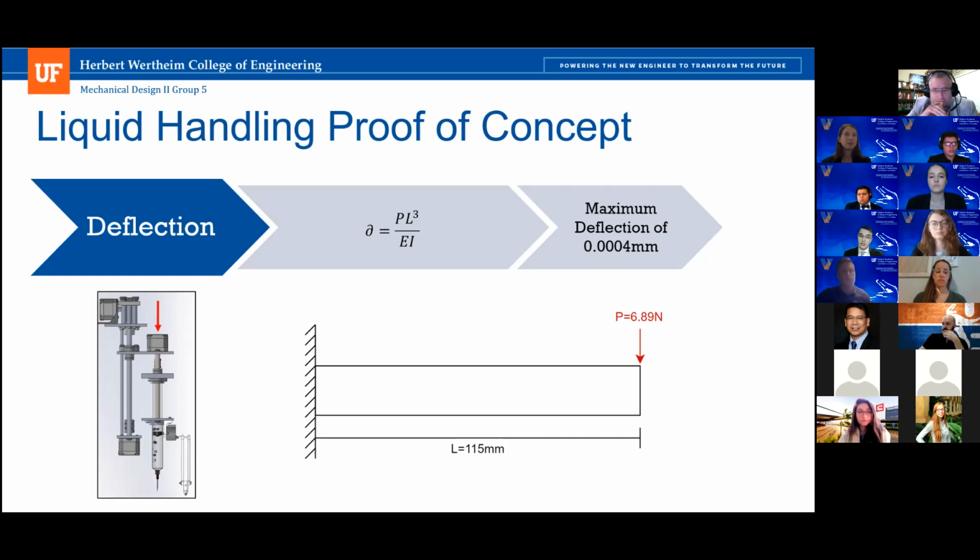You might want to move a little bit closer to the surface of the liquid. And so as you can see in this current orientation, if you went to insert this syringe into a well plate, you would certainly have interference with the measurement system and the surrounding environment. And so the motor there is designed to just rotate. It's a stepper motor, so we can rotate it 45 degrees, 90 degrees. And in this case, we would rotate it 180 degrees, completely vertical and out of the way so that all the liquid handling actions can be performed.